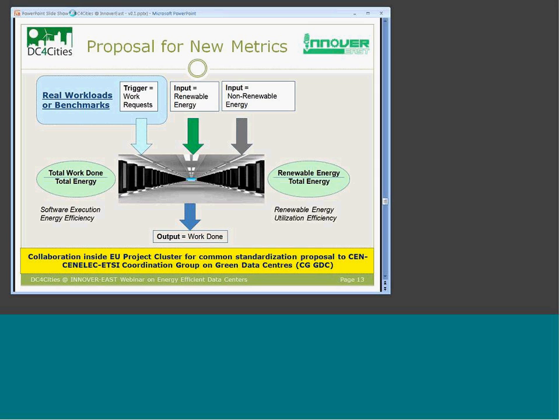The closer this ratio is to 1, the better. The ratio used to be well over 2 to 2.5, meaning there was a lot of overhead spent on air conditioning and UPS compared to the amount of energy spent by the computers. Modern data centers have a PUE of 1.25 or even lower. The world record is around 1.15 to 1.2 - these are very well optimized data centers.